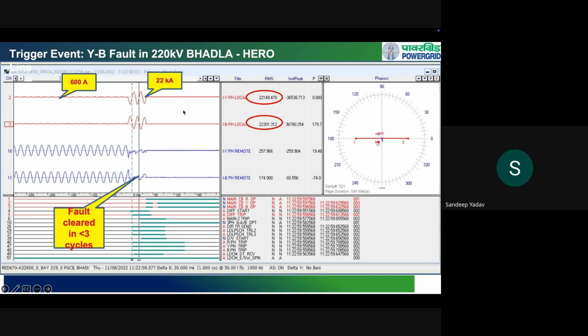Now, the pre-fault current: the solar generator was carrying about 206 megawatt of power, close to 200 megawatts, and the corresponding current was 600 ampere. The current from the grid side has risen from 600 amperes to 22,000 amps. However, on the solar generator side, the fault current, which was earlier 600 amps, is now only 257 in Y phase and close to 174 in B phase.